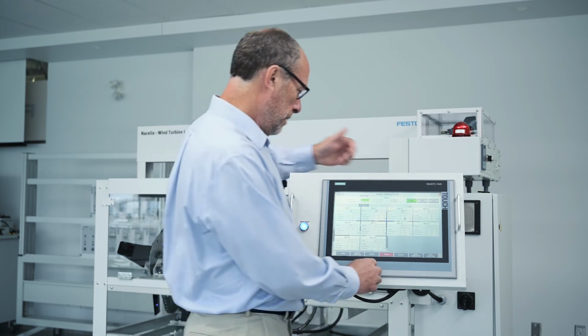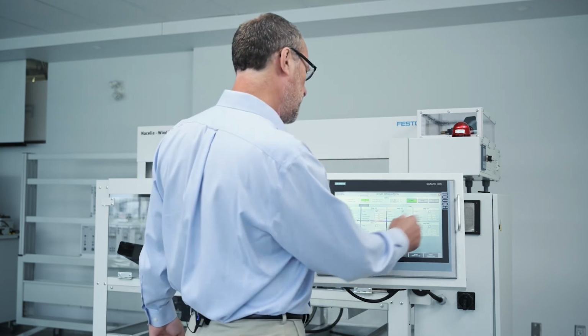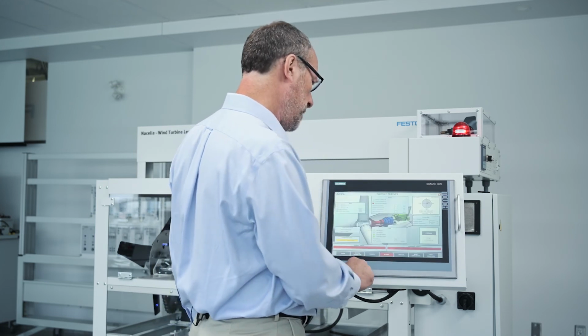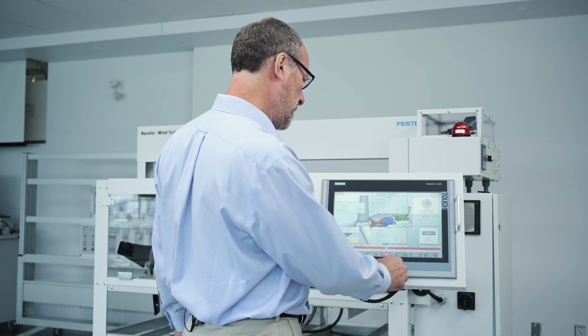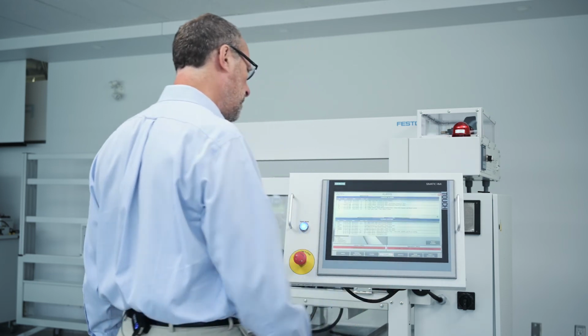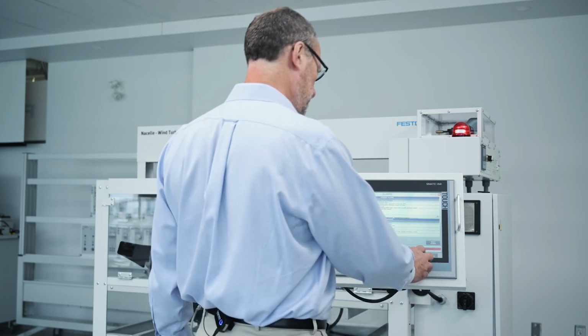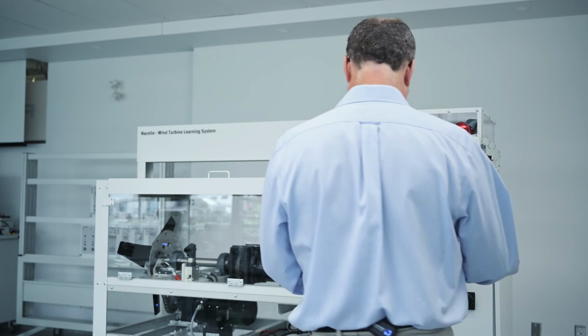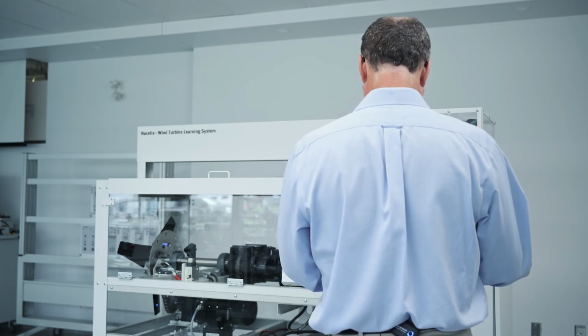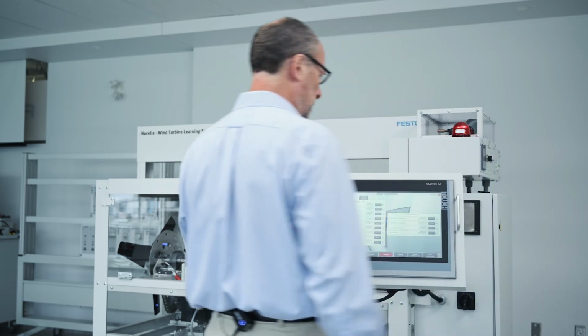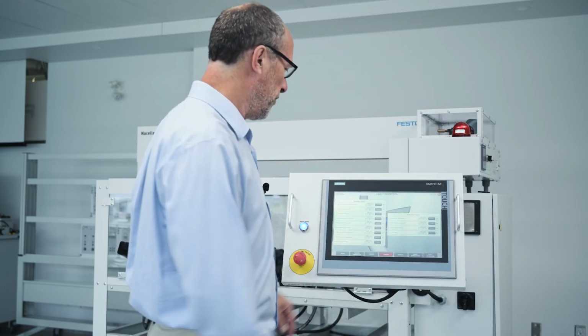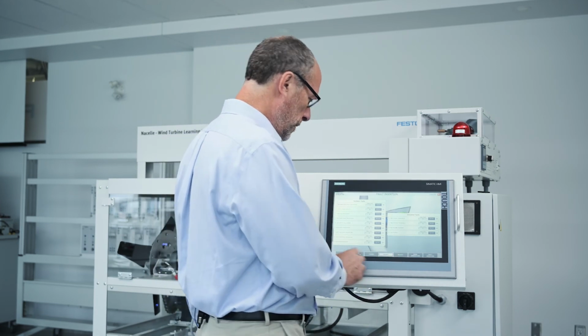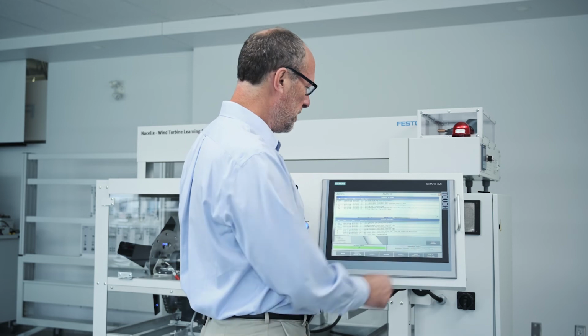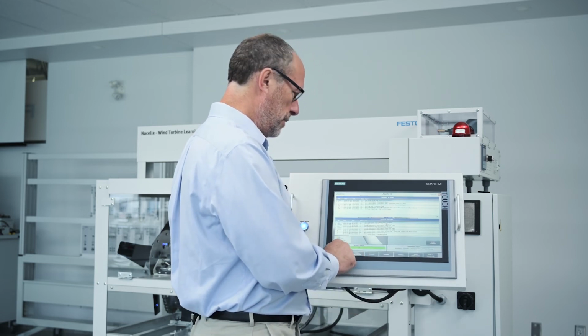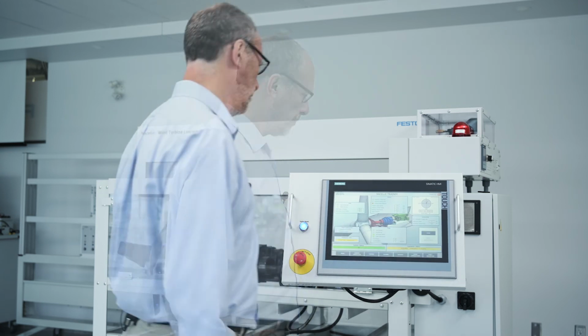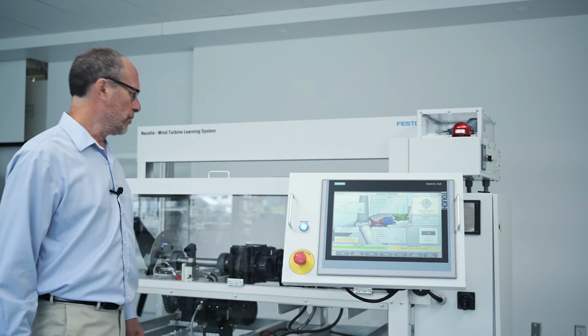And what you see now, okay, we can set this one start, okay. Main menu, okay. Now, I have an alarm. Okay, so if the student has done his work, then the teacher can go back into the fault insertion, remove the fault, and say, okay, now you've done your work. You can go back to the alarm and try to reset. Okay, it acknowledges, then we can restart the machine. And there you go. Machine is ready to start.